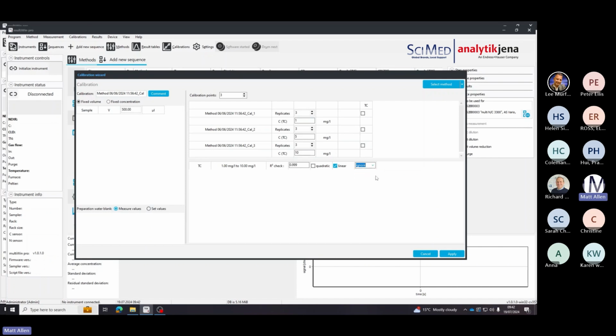So we can do a quick check on the calibration. On the bottom left you can see we've got a preparation water blank. So it's actually the carbon value of the water that's been used in the standard makeup. You can have this as set values, or you can get the system to actually measure it. So we'll get the system to measure the value. Once this is done, it's nice and easy. We can just press apply.